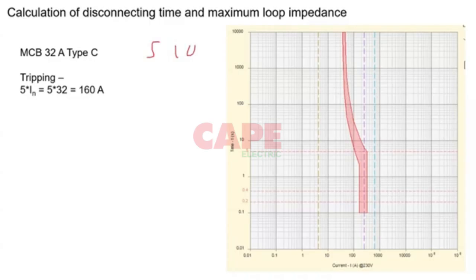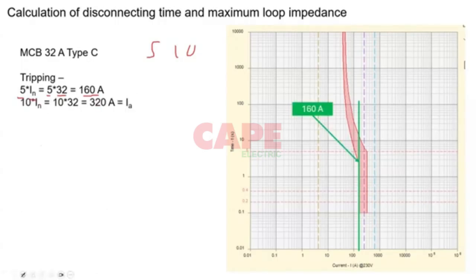So 5 into In, which is 5 into 32 amps, is going to be 160 amps, which is this green line. This is 160 amps. Next, you have 10 times, 10 into In, which is going to be 320 amps, which is this line. So while doing the fault impedance calculation, you are supposed to take the highest amount. You have to take 320 amps.